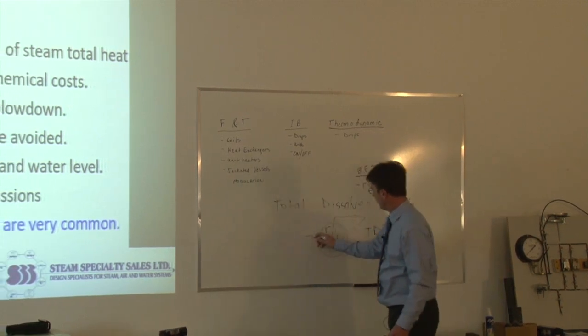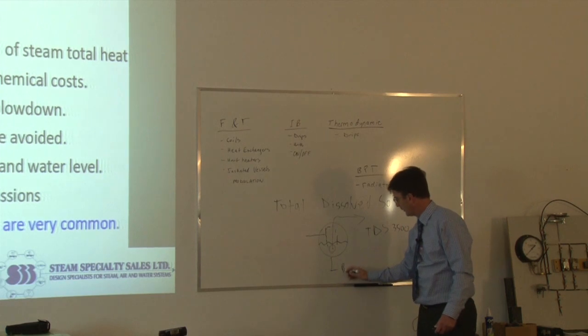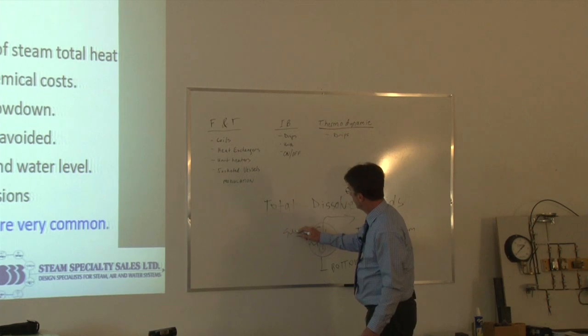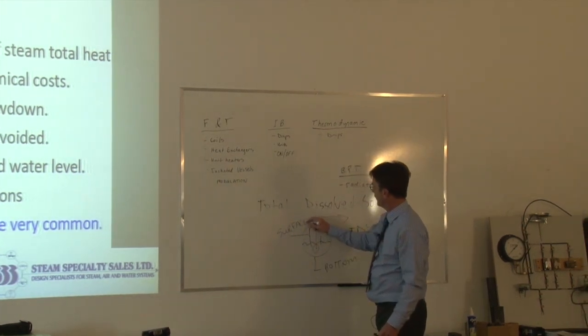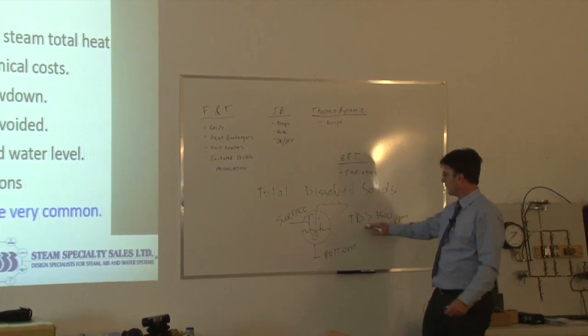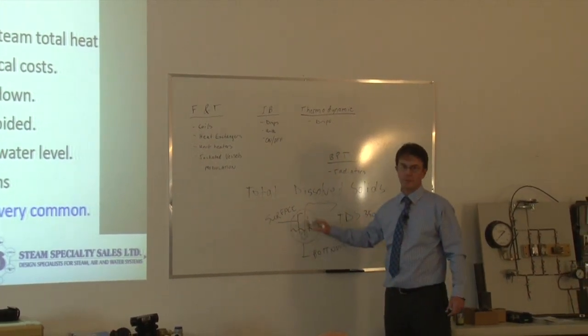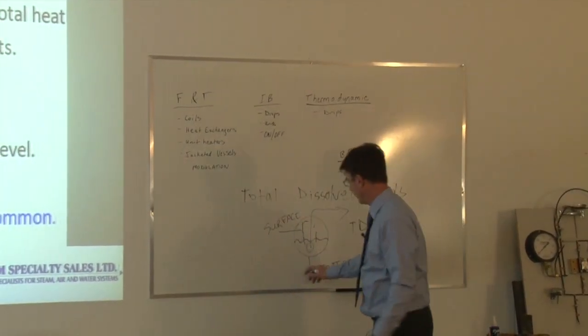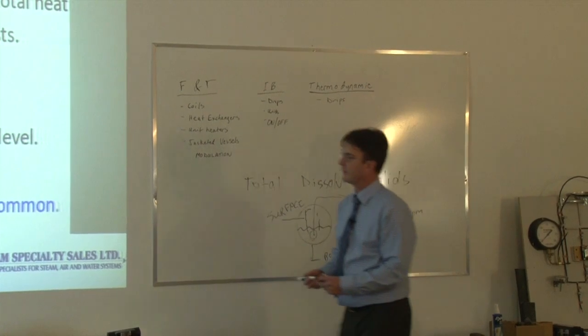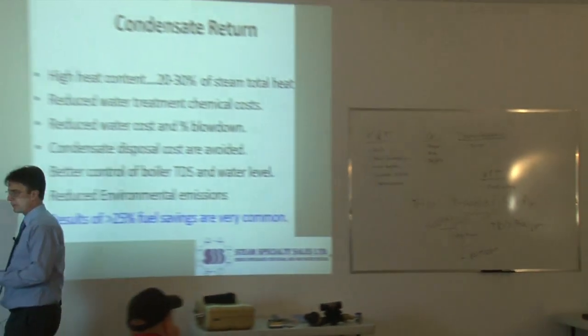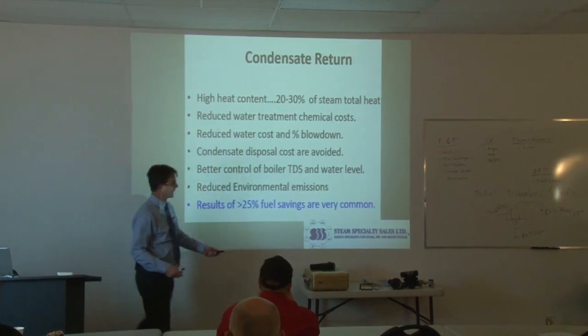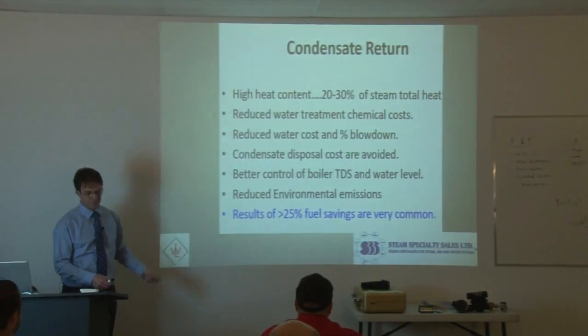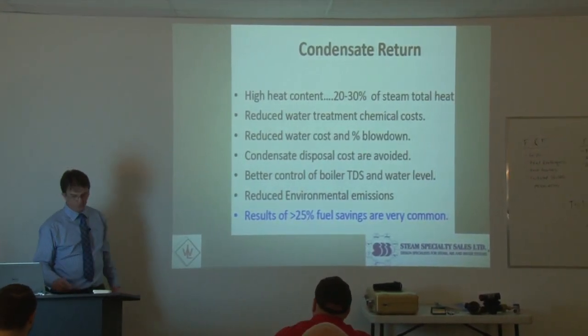There are two types of blowdown: surface blowdown and bottom blowdown. Surface blowdown, also known as continuous blowdown, controls the amount of total dissolved solids in suspension inside the boiler's water. Bottom blowdown is done a couple of times a day and gets rid of accumulated debris that can build up in the mud drum at the bottom of the boiler.